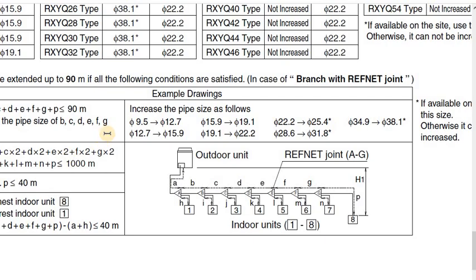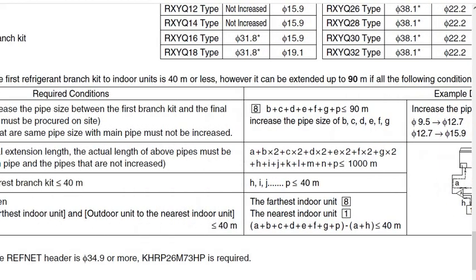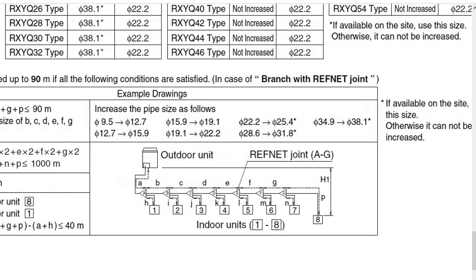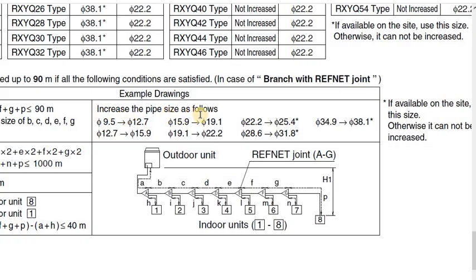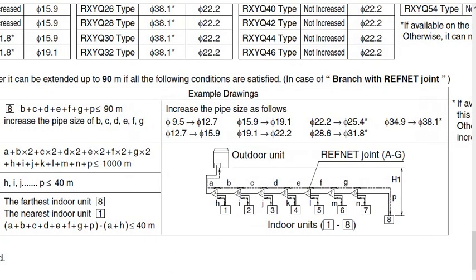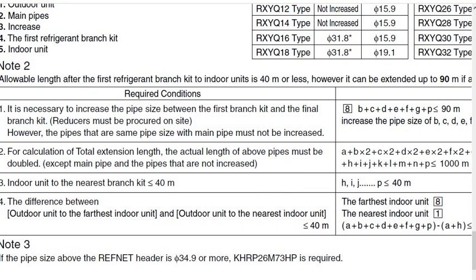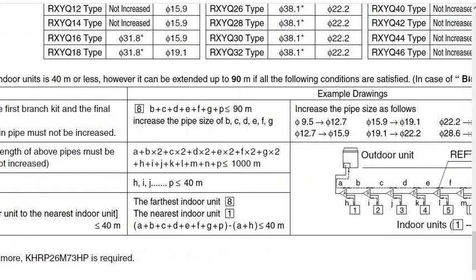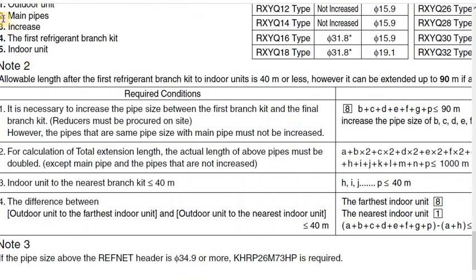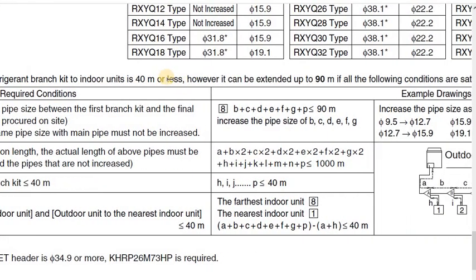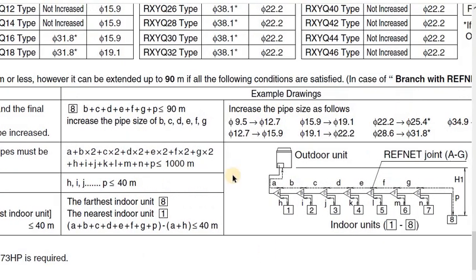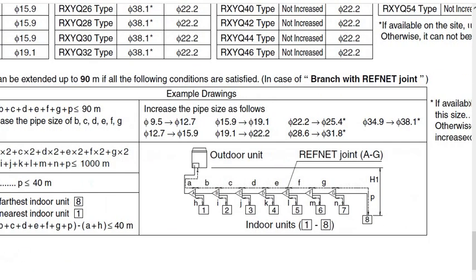Now friends, let's see how we can go up to 90 meters that we have discussed. If it is going above 40 meters, we have to increase the diameter of the pipe, increase the pipe size. These are the conditions. If it is going below, you do not have to do any arrangement. If it is going above, you have to increase. You can see here, the allowable length for the first refrigerant branch kit to indoor units is 40 meters or less. However, it can be extended up to 90 meters if all the following conditions are satisfied. You have to satisfy these conditions.